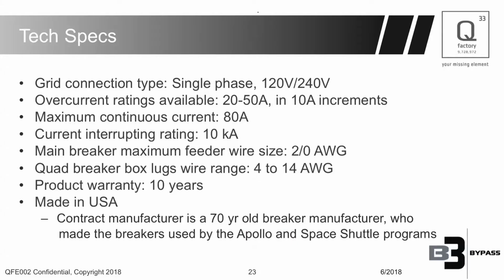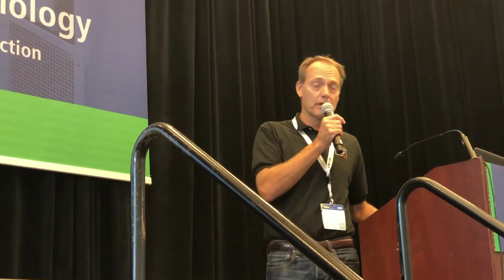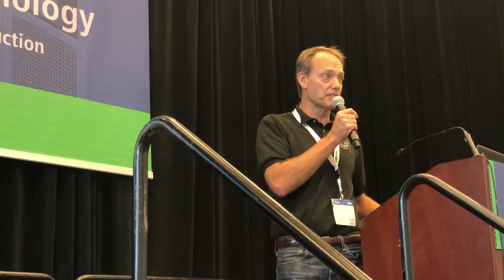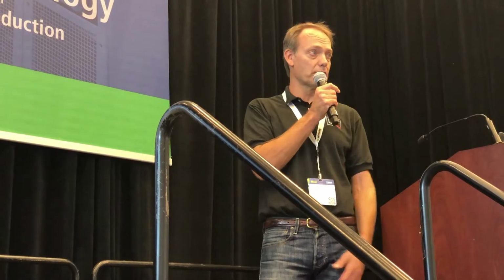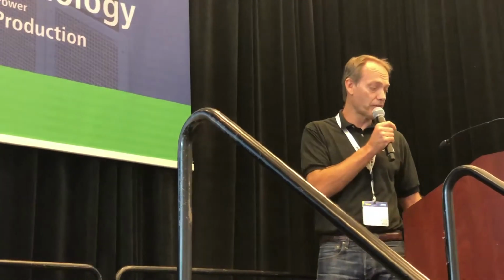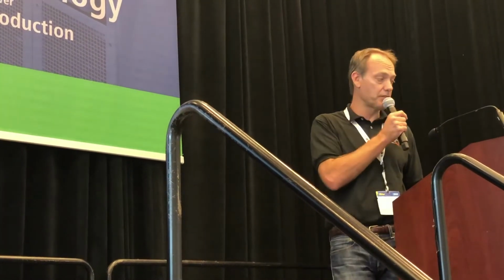All right, technical specs. The B3 bypass breaker is for single phase applications, 120/240. Overcurrent protection is in 10 amp increments from a 20-20 up to a 50-50 and all combinations in between. So for example, you could have a 20-40. If you have a 100 amp service, you need to pull an existing 20 amp breaker, and then you want to add, let's say, a 7.6 kilowatt inverter to that 100 amp service. That would be a 20-40, and combinations all the way up to 50-50.